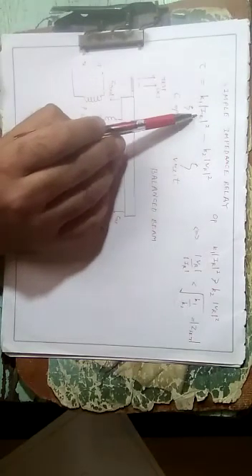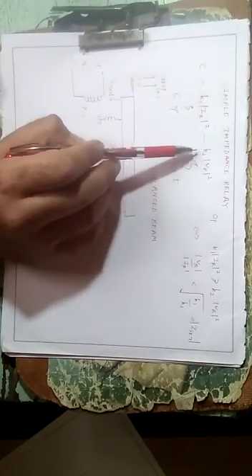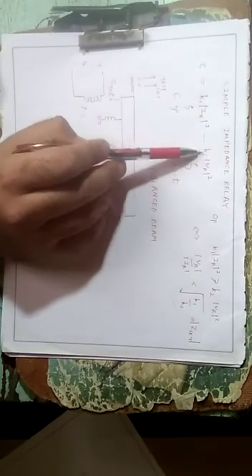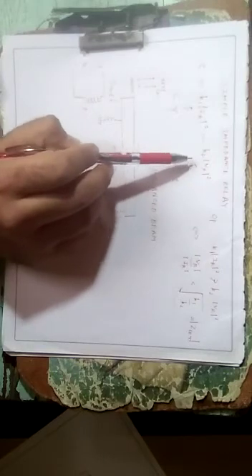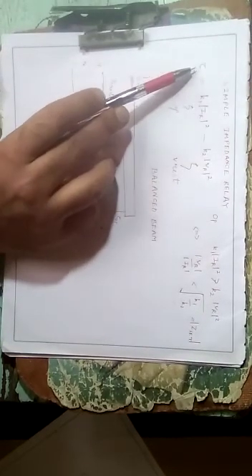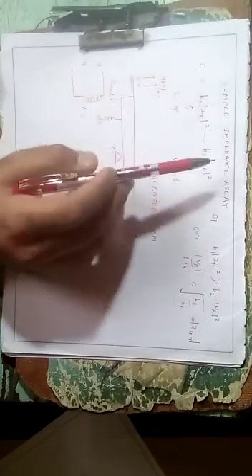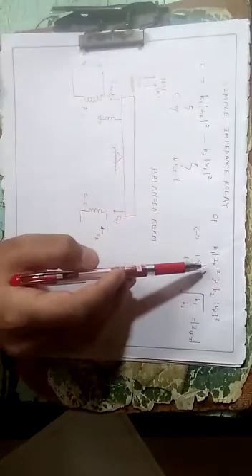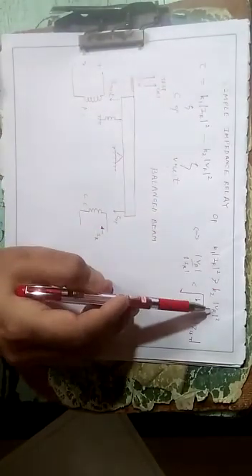Under normal conditions, the current term is dominated by the voltage term, because typically by adjusting these constants we can do that. Under normal conditions, the torque because of the voltage dominates the torque because of the current, and therefore the net torque becomes negative. The relay will not operate. For operation, this torque has to be positive, which is another way of saying that this is greater than this.